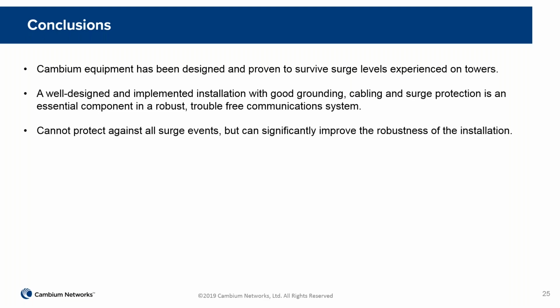So in conclusion, we have equipment that's been designed and proven to survive high surge levels, the sort of surge level that we would see on towers. But that equipment must be coupled with a good installation. So the installation has to be well thought out and implemented. We need the right grounding, cabling and surge protection devices, and with the combination of those components, we should end up with a robust and trouble-free communication system.